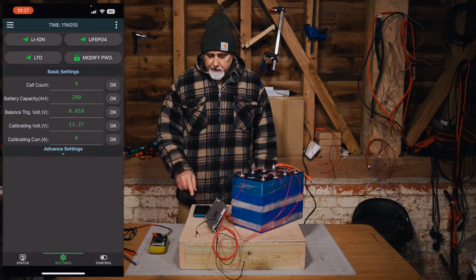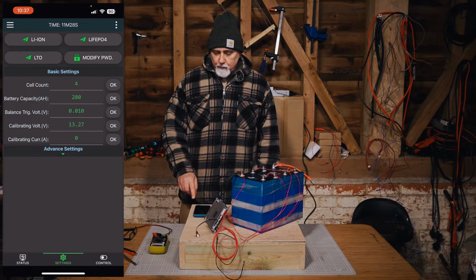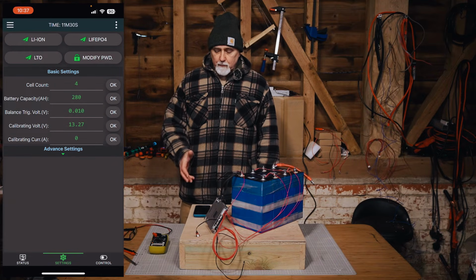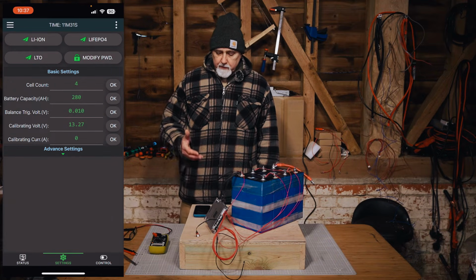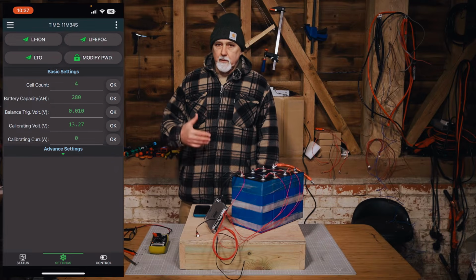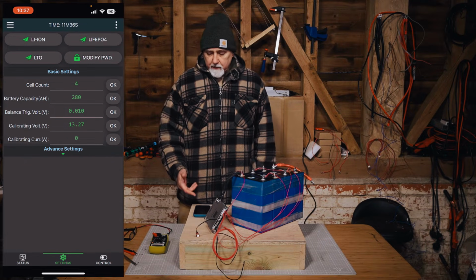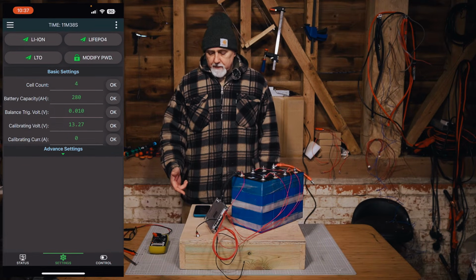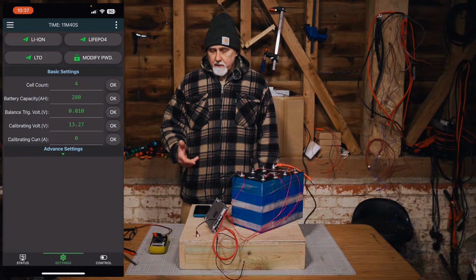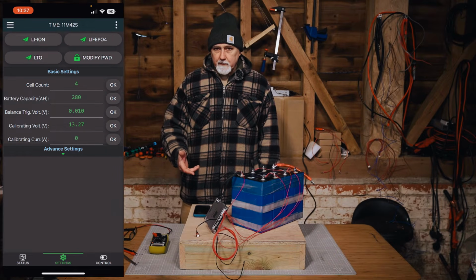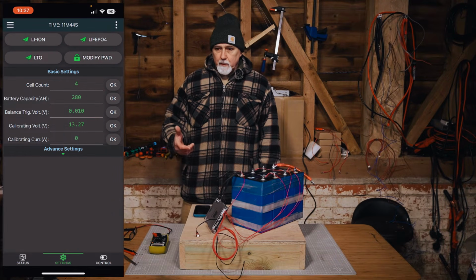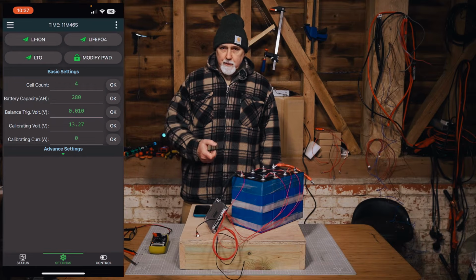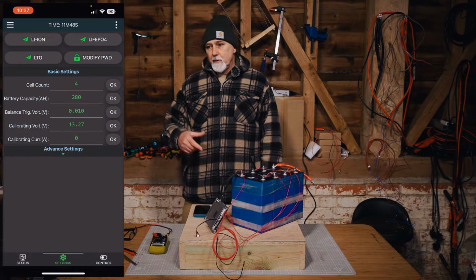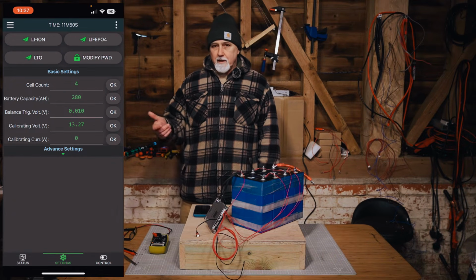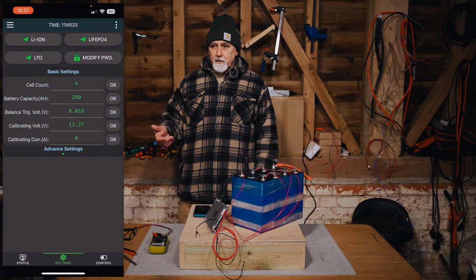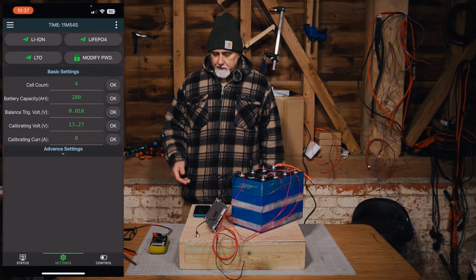Coming back to this, the calibrating volts, if you want it to say exactly what your multimeter has read, you can change it, and same with the current. But bear in mind, the BMS does not take into account the Peukert effect. So if you want it to be accurate at a low amperage, you can set it, or if you want it accurate at a higher amperage, you can set that, but it probably won't work both ways at once.